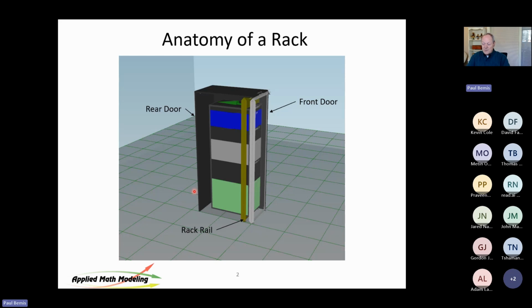The doors are not really consequential. The doors, you really don't need to model because they're pretty much 80–90% area open. And if they're not, that's a problem, right? You don't want the door restricting airflow because the air is going front to back. So this rear surface and this front surface really don't even need to be there. They could be eliminated. They're not, of course, because people have doors on their racks and you like to close them. But they need to be highly open, and therefore we don't worry much about them from a modeling point of view. It's rare that I ever model doors.